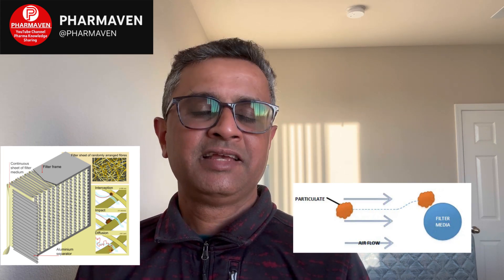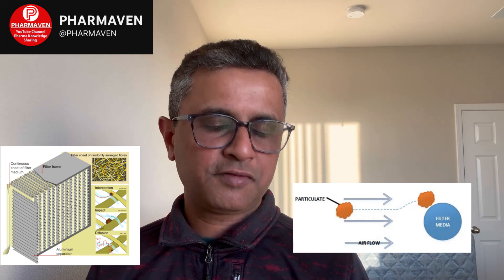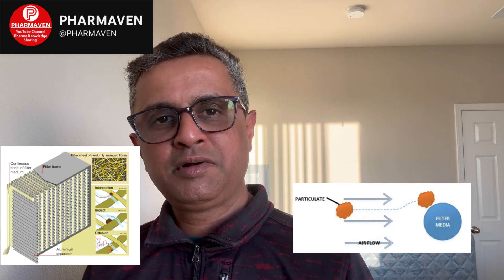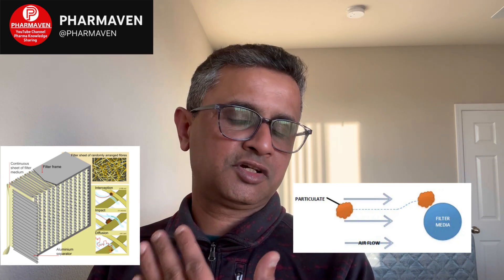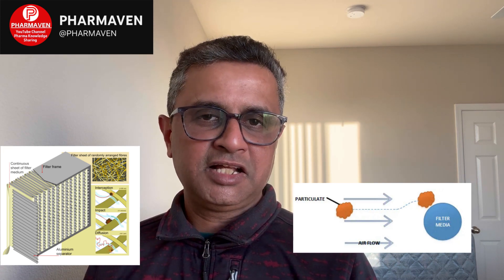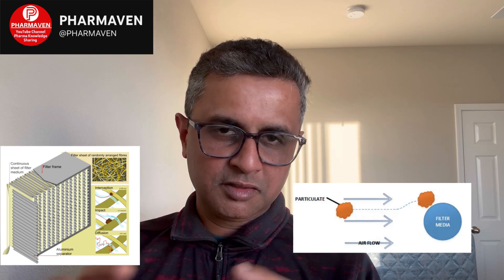Because of their very small mass and very small size, these particles get attached to the fibers and get filtered. In interception, very small particles — when they pass through the HEPA filter and come in contact with the fiber structure — attach to it. The particle size is smaller than the pores, so they travel through the pores, but the moment they contact the fibers they attach and do not go beyond, retaining particles smaller than 0.3 micron.